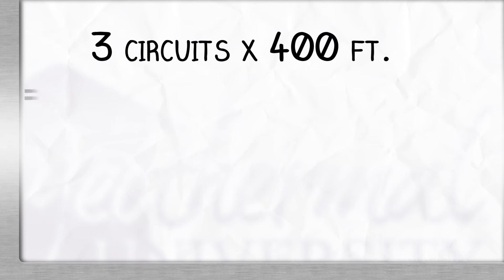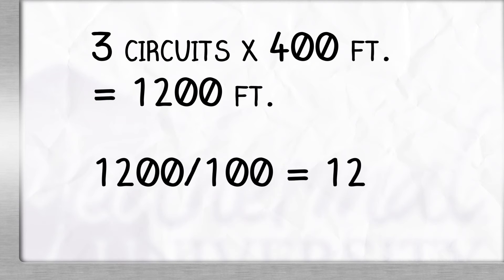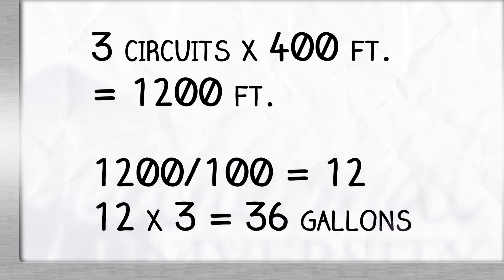So, our calculations are 3 circuits times 400 feet equals 1,200 feet. 1,200 divided by 100 equals 12. 12 times 3 gallons equals 36 gallons.